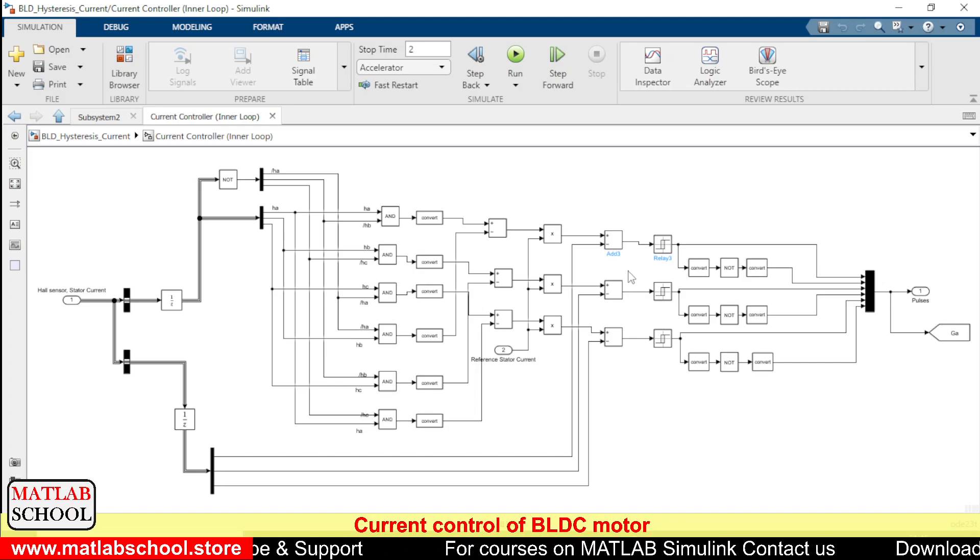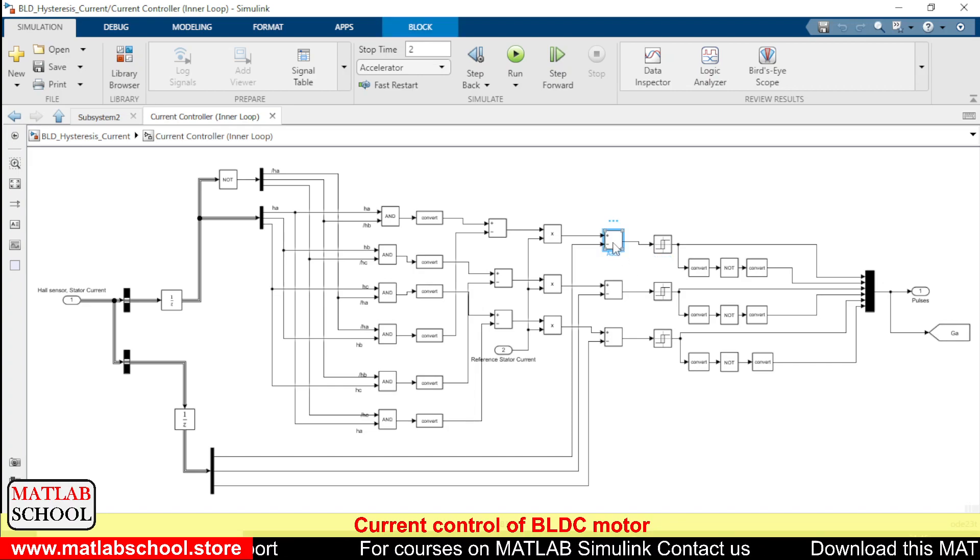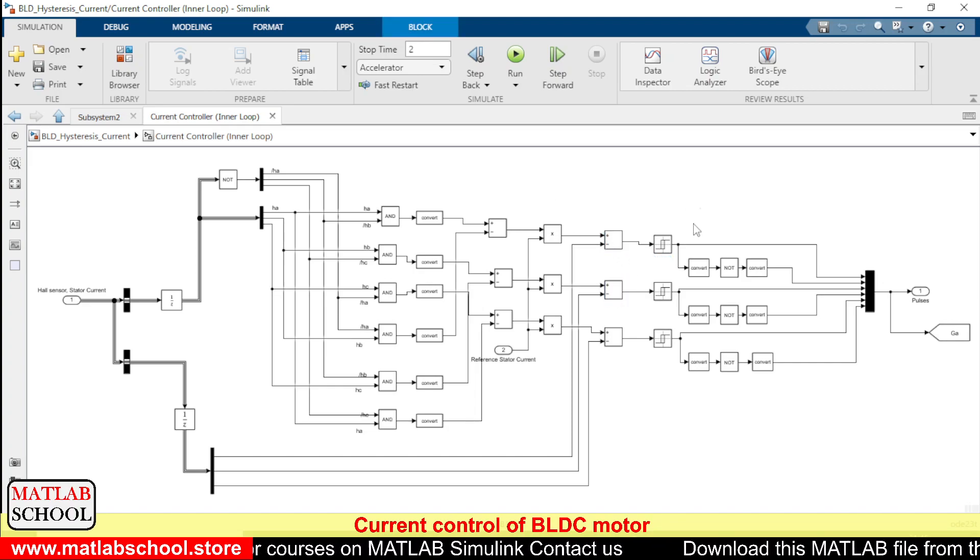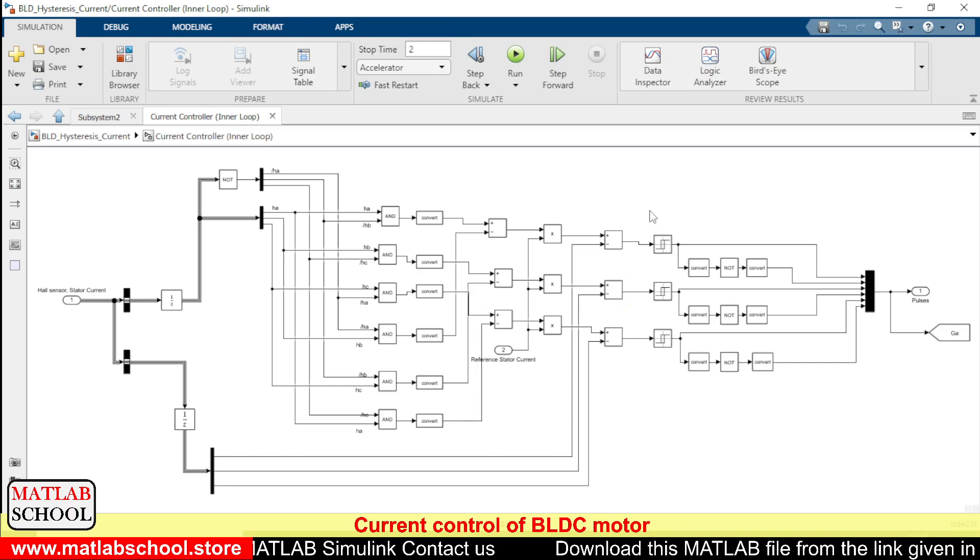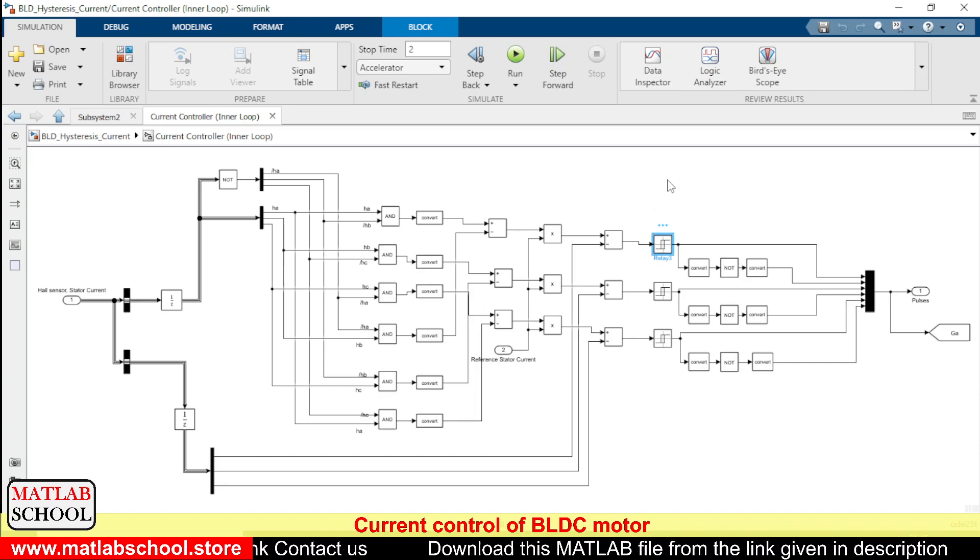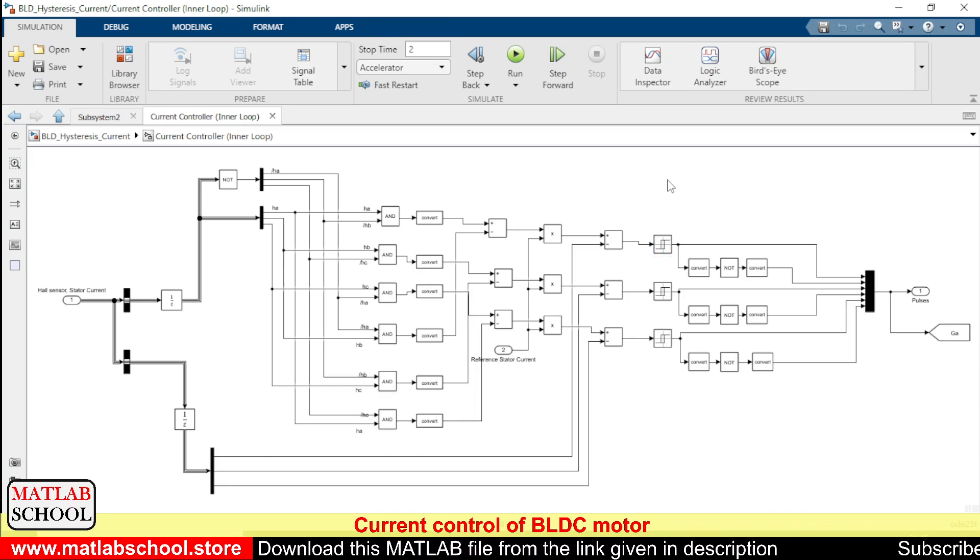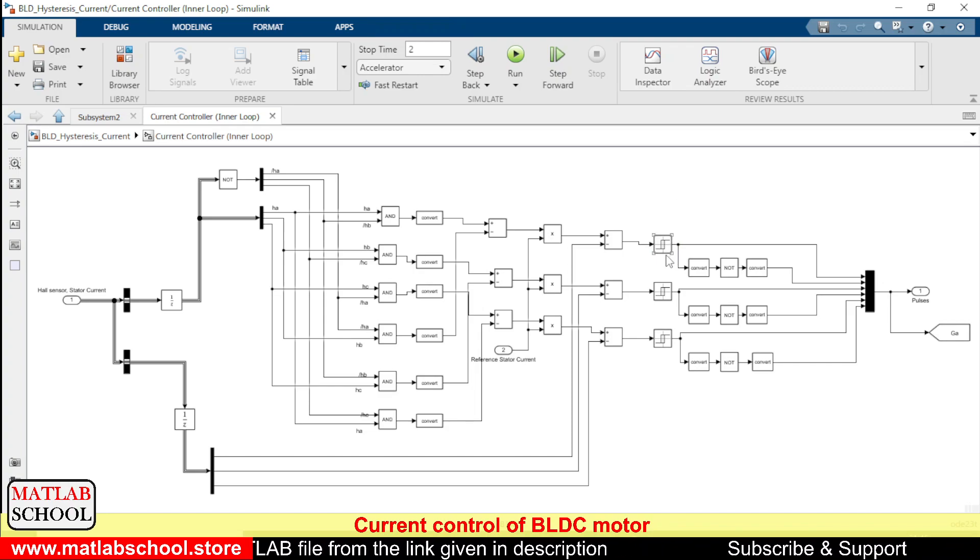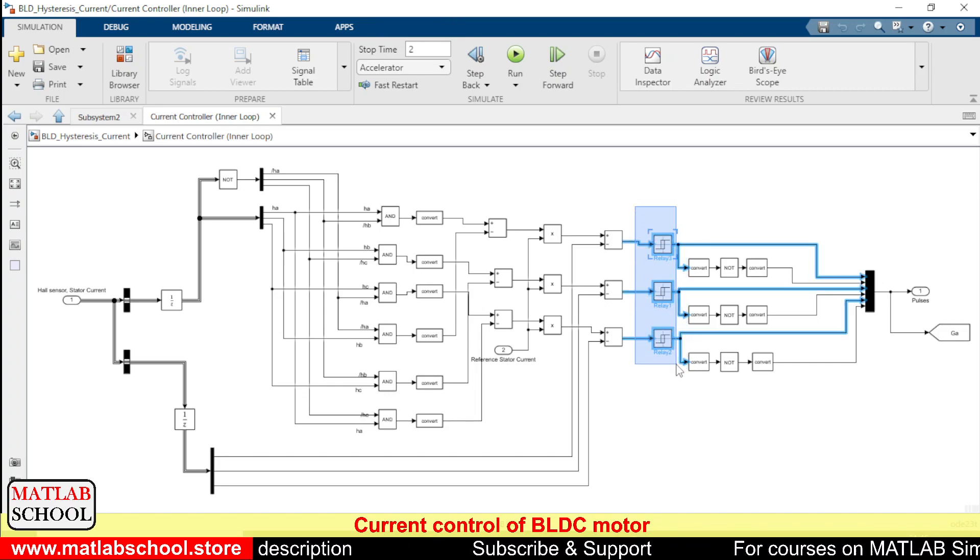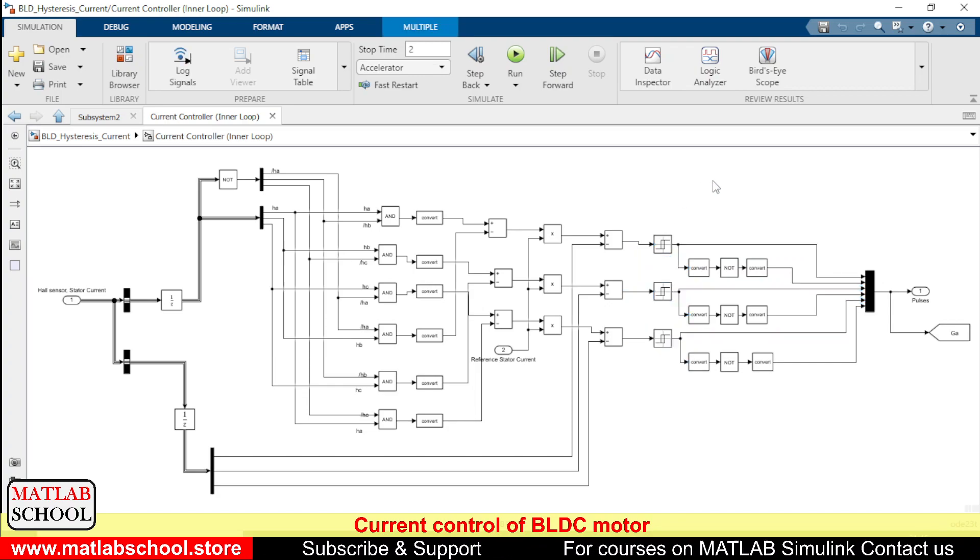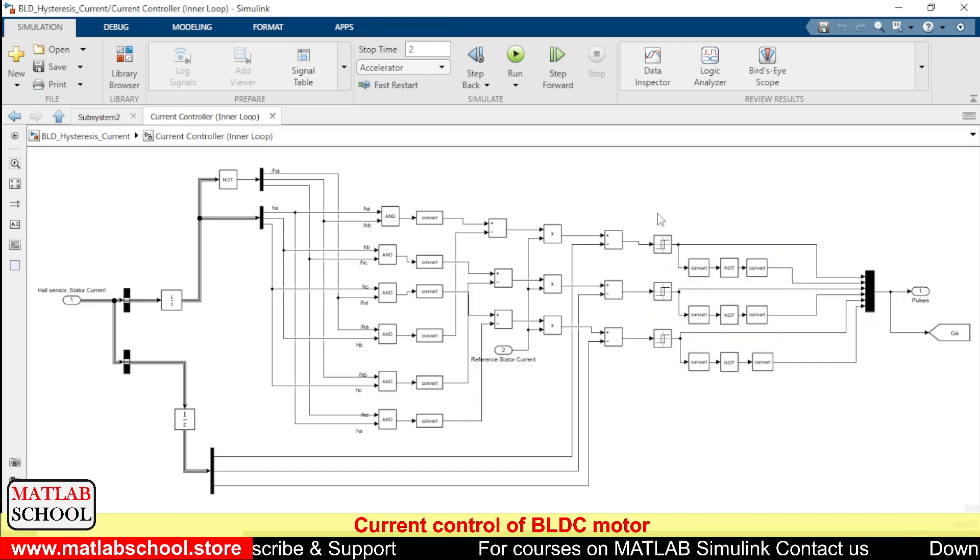And as you can see here we will be comparing the currents. And if there is an error, based on that error either we will be switching on the switches in the inverter or we will be switching off the switches in the inverter. So this is the hysteresis controller that we have in the inner current loop control. So this is responsible for controlling the current.